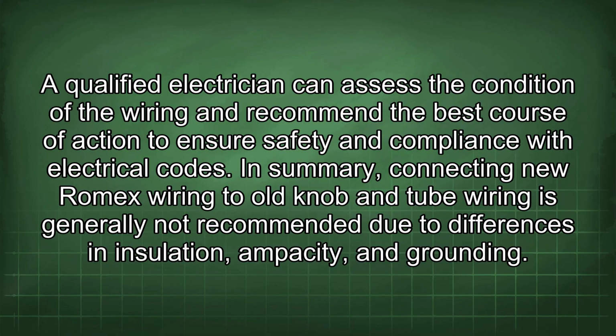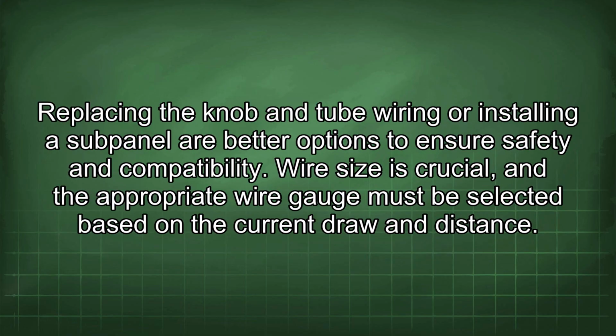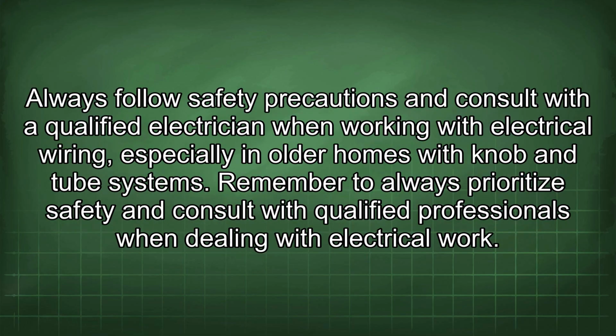In summary, connecting new Romex wiring to old knob and tube wiring is generally not recommended due to differences in insulation, ampacity, and grounding. Replacing the knob and tube wiring or installing a subpanel are better options to ensure safety and compatibility. Wire size is crucial, and the appropriate wire gauge must be selected based on the current draw and distance. Always follow safety precautions and consult with a qualified electrician when working with electrical wiring, especially in older homes with knob and tube systems.